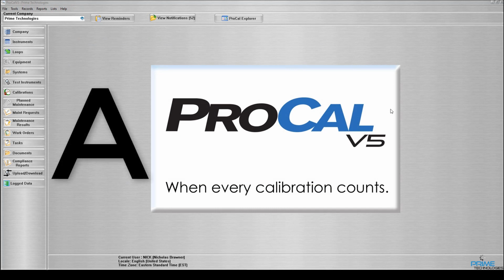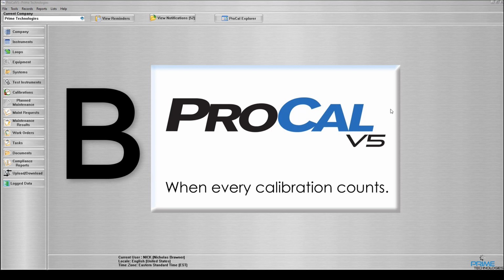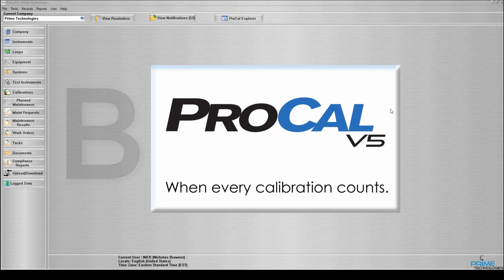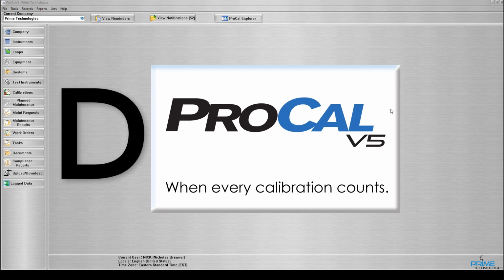A means that all as found and as left readings have passed. B means that there were as found failures outside of the CTL value, but all as left tests have passed. C means that there were as found failures outside of the PCTL value, but all as left tests have passed.